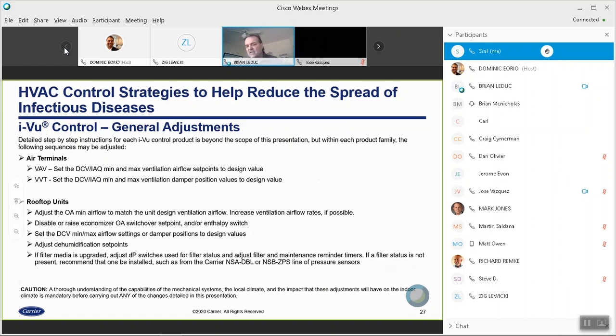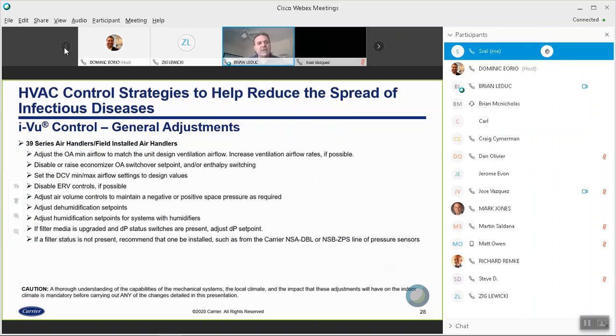Again, the NSA and the NSB line has some suitable sensors that can be used for that purpose. Air handler units, you're going to have a bit more flexibility there, because if you're dealing with a field install control on a Carrier 39 series air handler, or somebody else's air handler with field install controls, you probably program that either with library logic or logic from your own design.